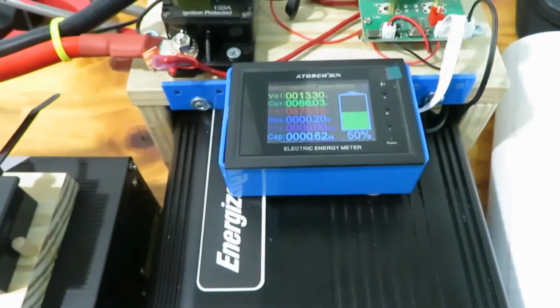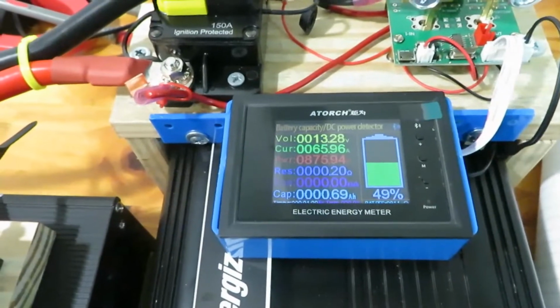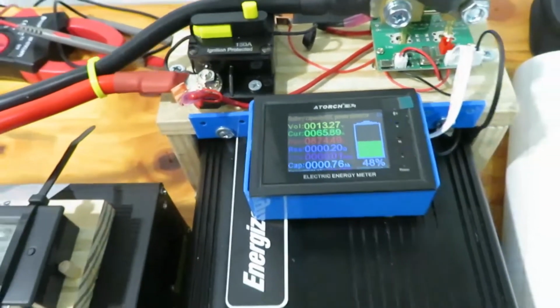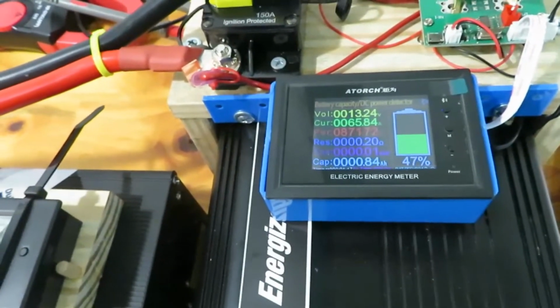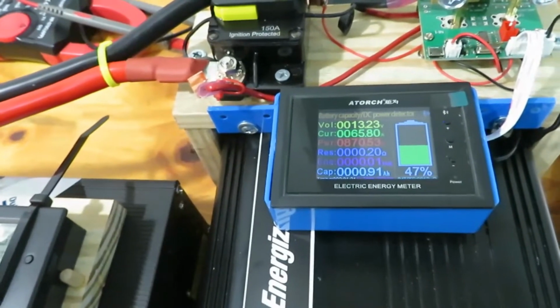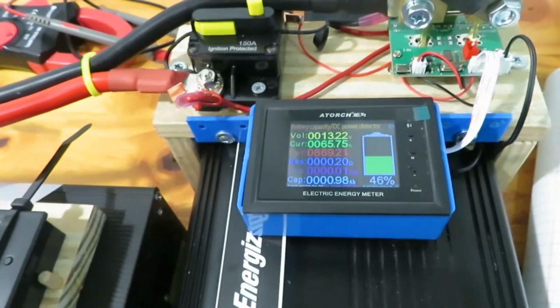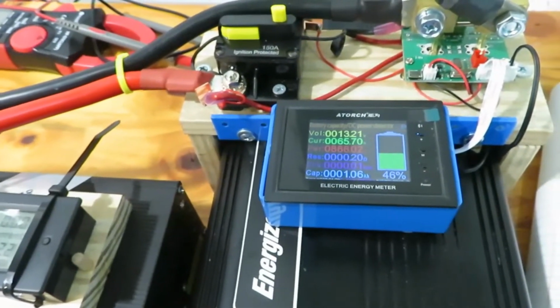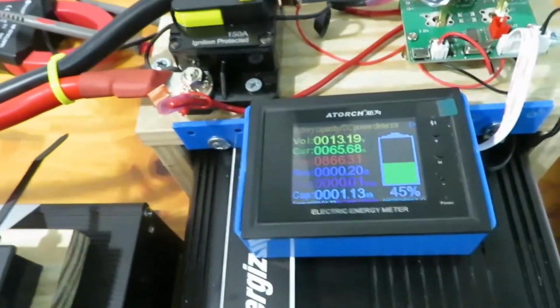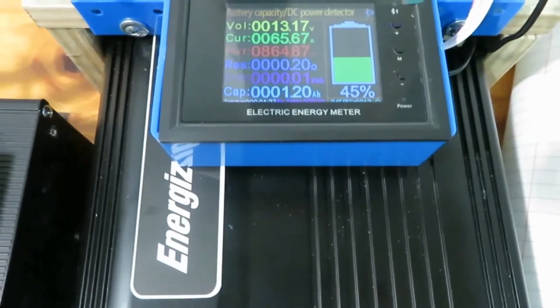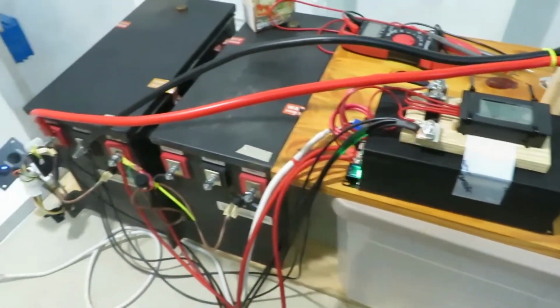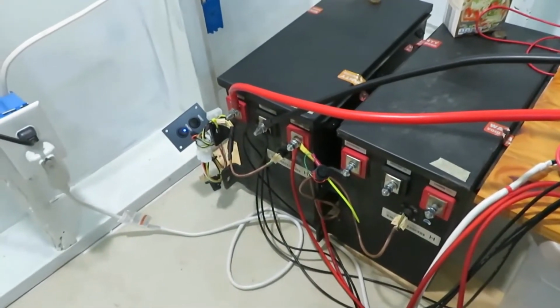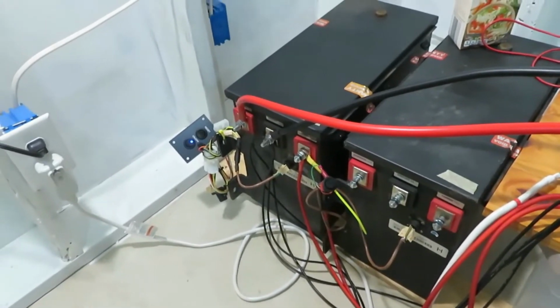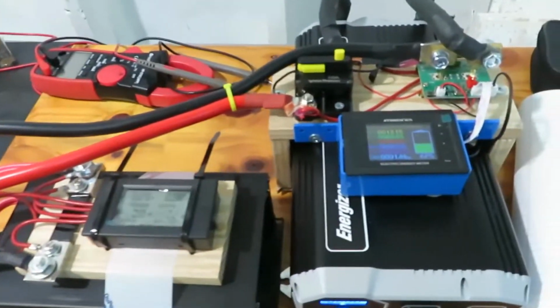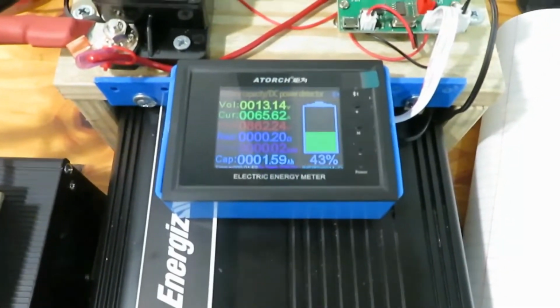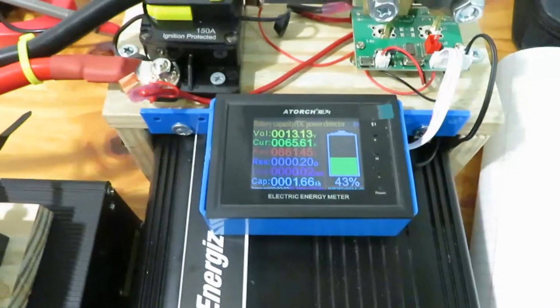So the battery voltage is drawn down to 13.27 volts. This should take about 3 hours to discharge a 200 amp hour battery. So we'll come back in about 2 or 3 hours. Hopefully I could catch it before it goes offline. But if it does go offline, we already have the amp hours recorded. And my plan is to draw down the battery until the BMS shuts it down completely. Once the BMS shuts it down completely, then we know what the low capacity of this BMS is. So we'll come back in a little while.